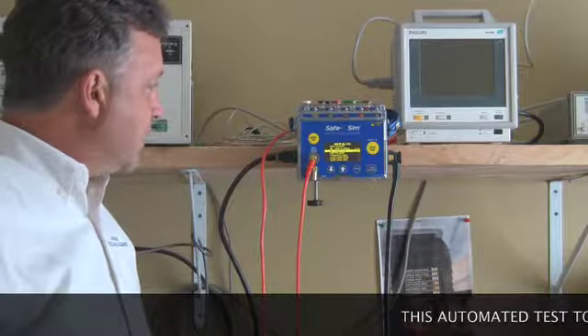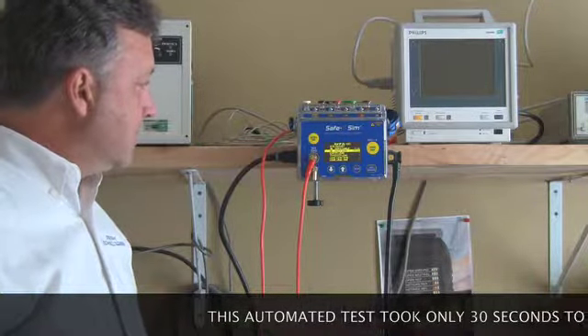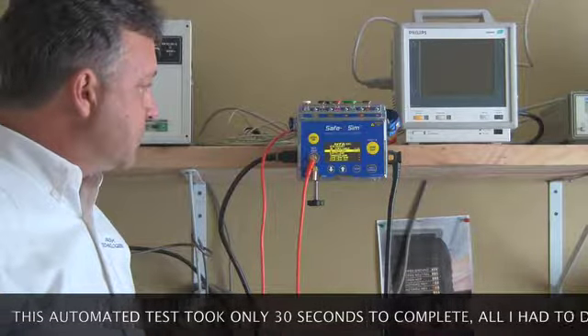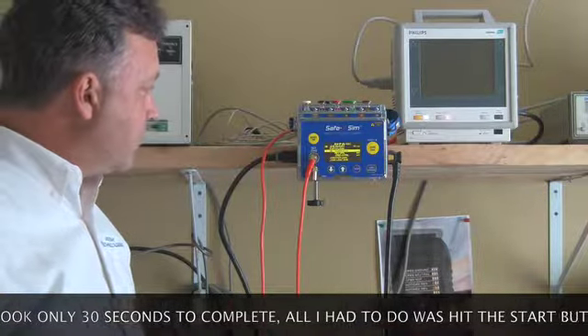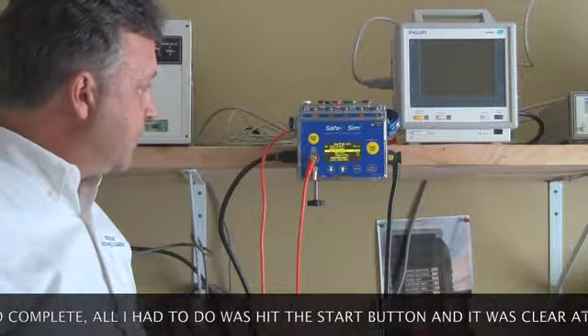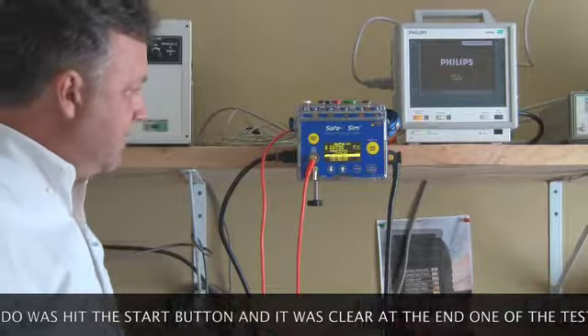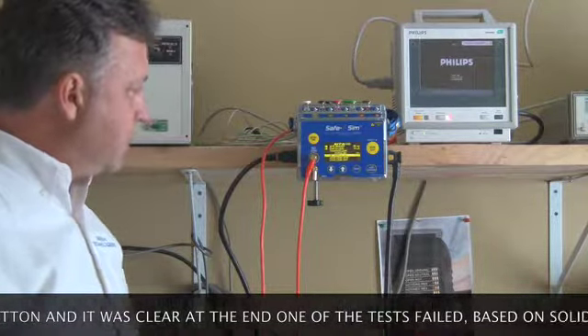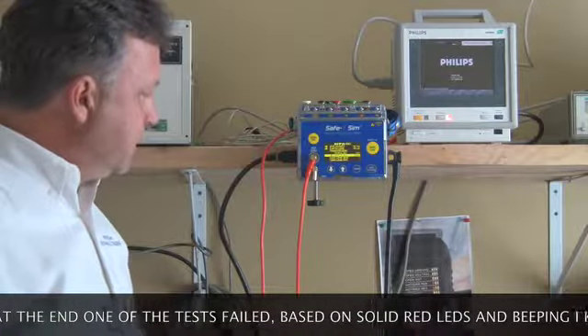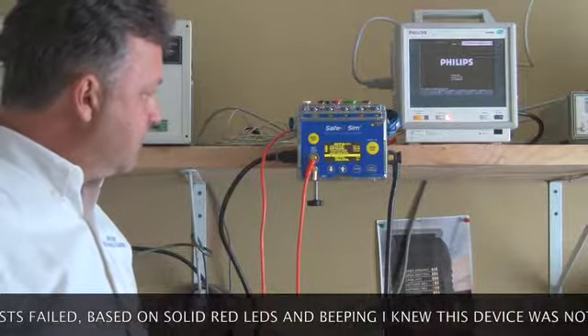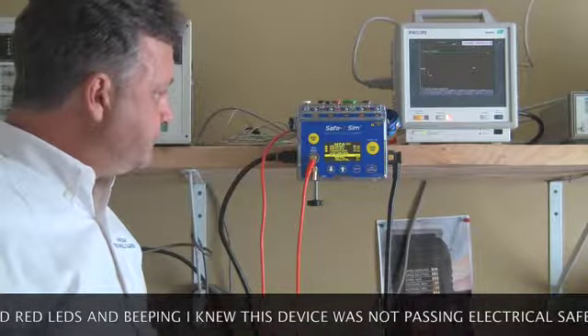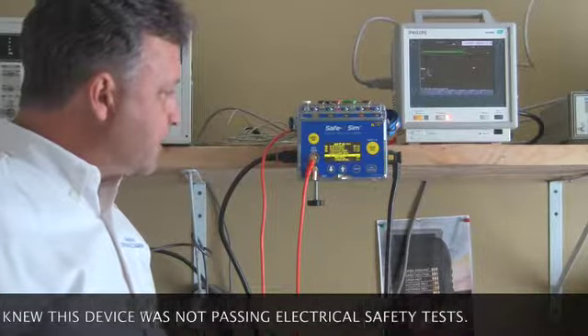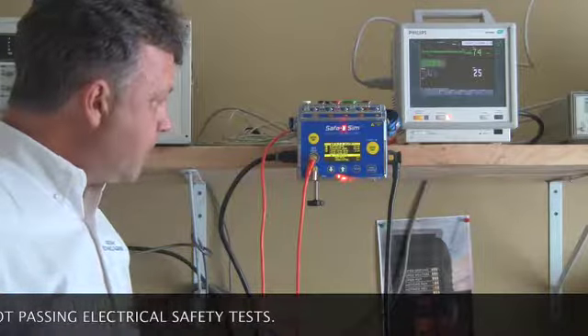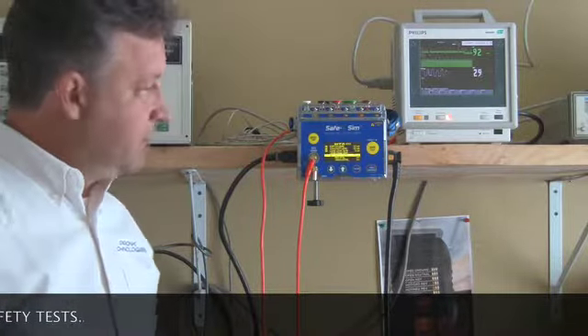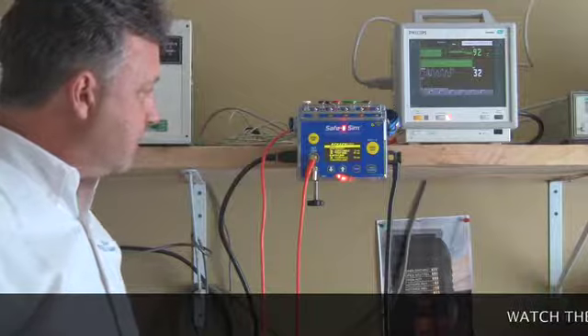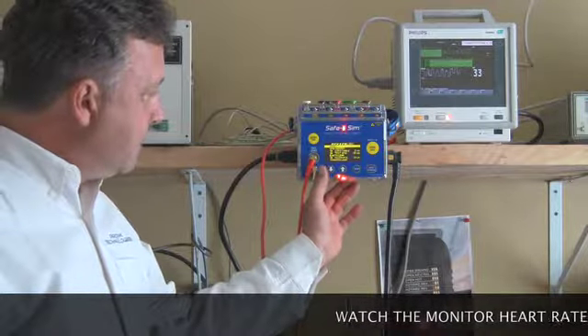There it is doing the test ground. It sees a good value for the ground resistance. It moves forward with a green flash. Earth leakage normal polarity is running now with an hourglass. It's done with a green flash. Chassis leakage failed. And it failed because I set that limit at 5 microamps, which is much lower than the standard of 300 typically. So we finished the test.